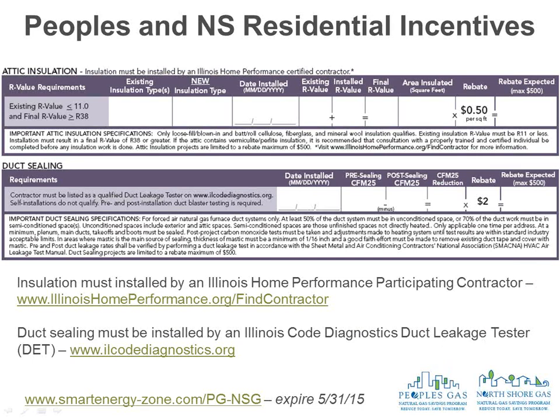And then additionally, there's a duct sealing rebate. This did change a little bit. It used to be $3 per CFM reduction. Now it's $2 per CFM reduction, but the maximum is still $500. I know some of the Aeroseal dealers were concerned about that, but we started looking at it, and pretty much when you do Aeroseal, you max out on the $500 either way. So the 2 or 3 is pretty irrelevant for the Aeroseal guys. If you're doing things by hand, maybe it makes a little bit of a difference. But basically, you have to test in and test out.